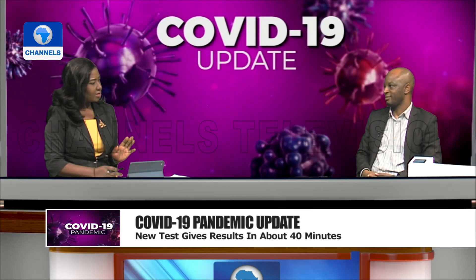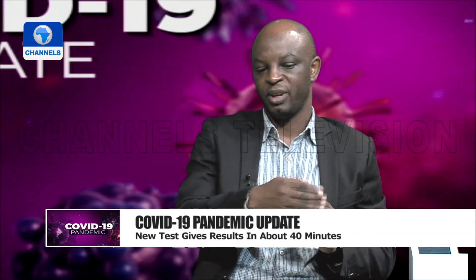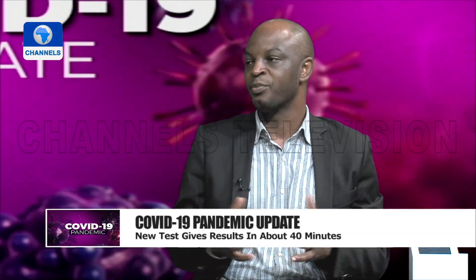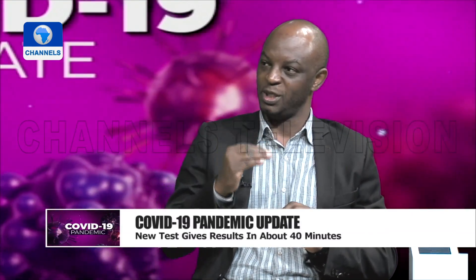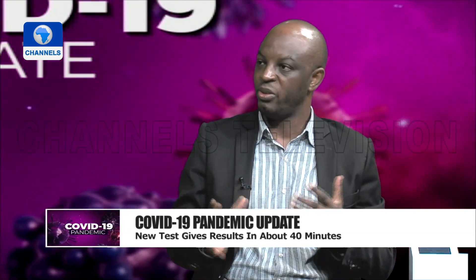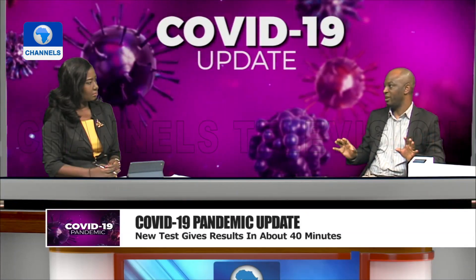You said it is fast, but what do you mean when you say it's sensitive? Sensitive is how low it can detect — in terms of viral copies — and also if it can detect different types of strains of the virus. We are a testing lab for COVID, so we had access to samples and tried it. We are able to get it to detect as low as 100 copies per milliliter. If a sample has at least 100 copies per milliliter, we guarantee we'll detect it. It actually went as low as 16, but it wasn't consistently picking up everything between 100 and 16, so the consistent guaranteed threshold is 100. For something this small that can go to any clinic, it's really very good.